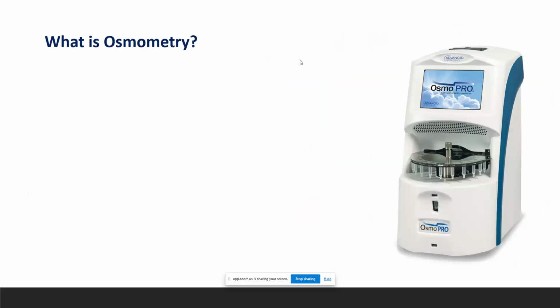So moving on to osmometry. What is it? It's a technique for measuring the concentration of solutes that contribute to the osmotic pressure of a solution. Most modern osmometers share a common principle in that they measure the osmolality of a liquid sample by comparing a particular parameter of the solution, such as its freezing point, to the same parameter of the pure solvent, for example, water.